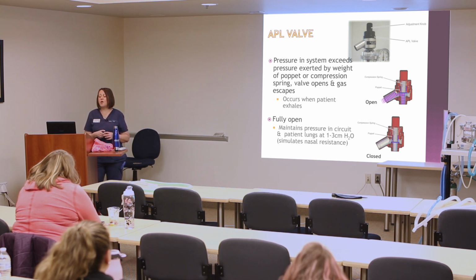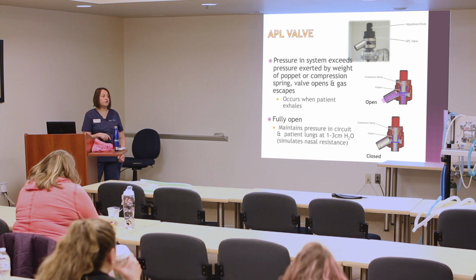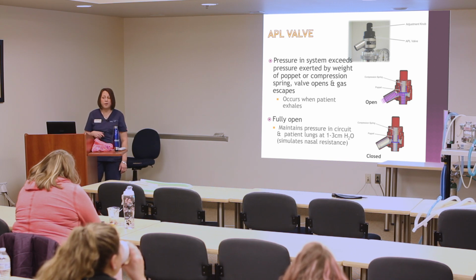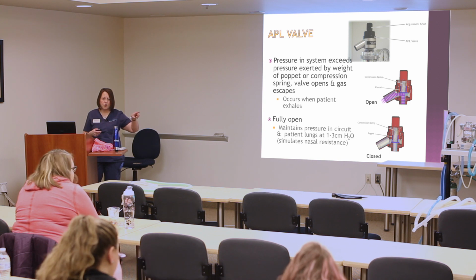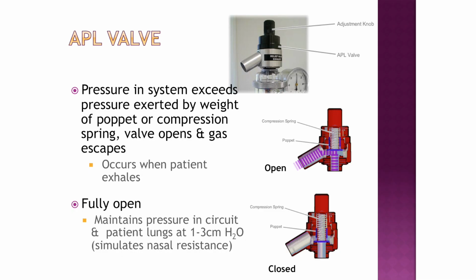I will tell you though that if this is shut and you try to use your machine, you can kill something, which is why these new blue sections have shown up. These positive pressure relief valves have shown up on all the machines. You're not to ever take them off. And I will show you how it works if somebody did leave the pop-off shut on you. But fully open, they're technically supposed to simulate nasal resistance, keeping a little bit of pressure in there, 1 to 3 centimeters. It's pretty minor.